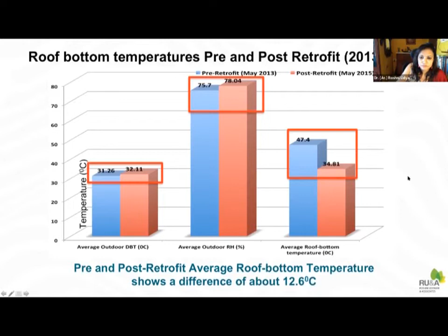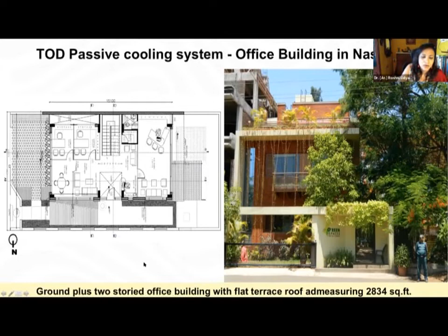The second example is a TOD system, a thermal drain system, which reduces the use of air conditioning entirely. There was no air conditioning in this office building in Nashik, ground plus two storeys, 2,834 square feet. You can see the pipes being put up here. These pipes are embedded on top of the roof, and water is circulated through them. The system is designed to remove heat from the structure at about 242 BTU per square foot per hour.